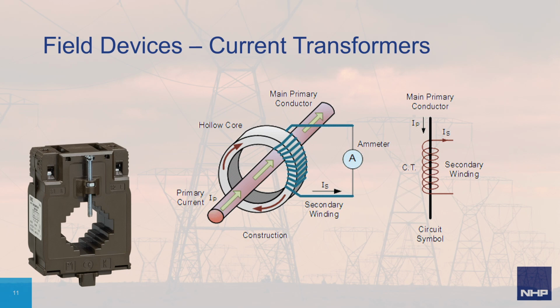The humble current transformer, or CT, is a very important primary device in energy management. It allows a potentially very large current to be transformed down to a small, easily measured current, usually 5 amps, for measuring devices such as energy meters. And we'll look at those next. The CT has an iron core with a hole through the center for the primary current carrying conductor. The primary current flow causes a magnetic flux around the conductor, which induces a flux in the CT core. This flux links with the secondary winding wrapped around the core as shown in the image.